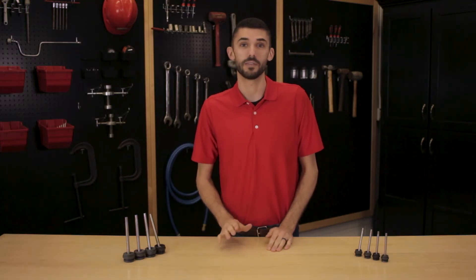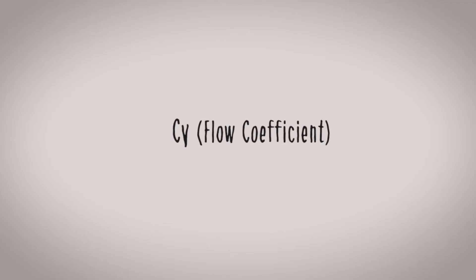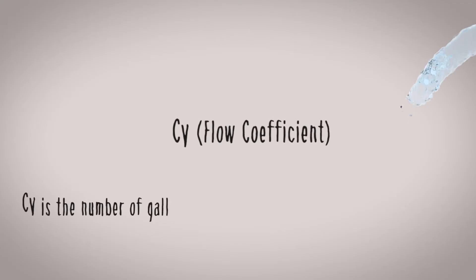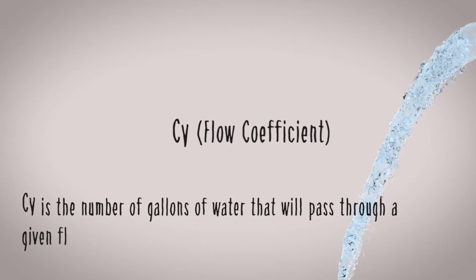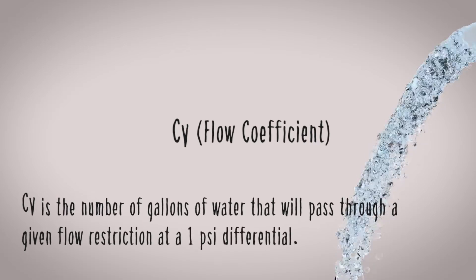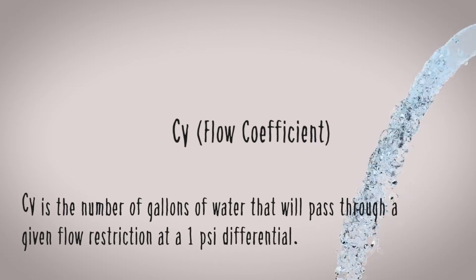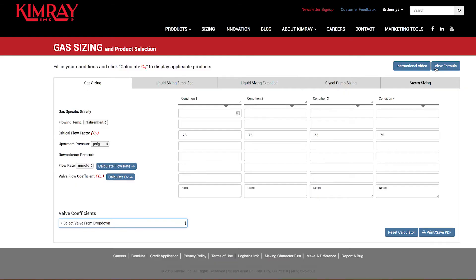I know it sounds obvious to choose a high pressure valve for a high pressure application, but there's another key factor you need to consider: calculated CV. CV is the number of gallons of water that will pass through a given flow restriction at a 1 psi differential. Basically, you can think of it as the orifice size of a valve.